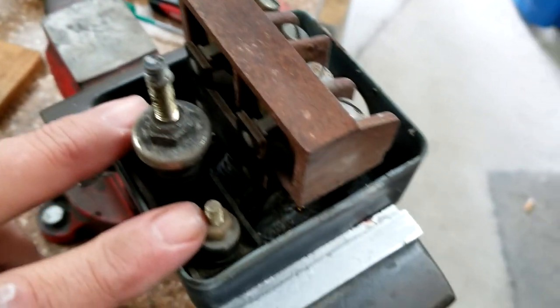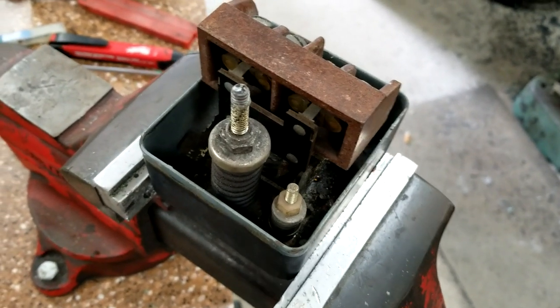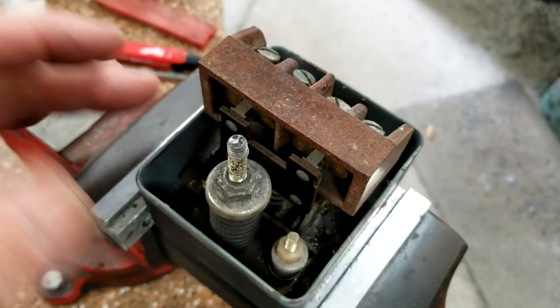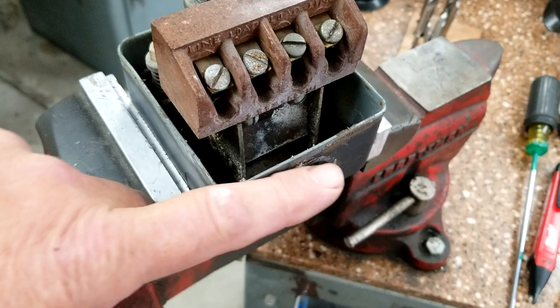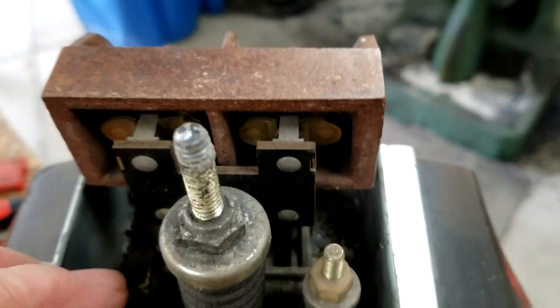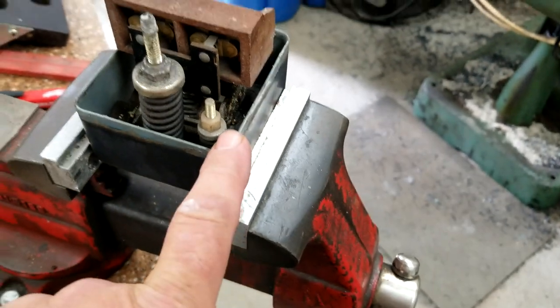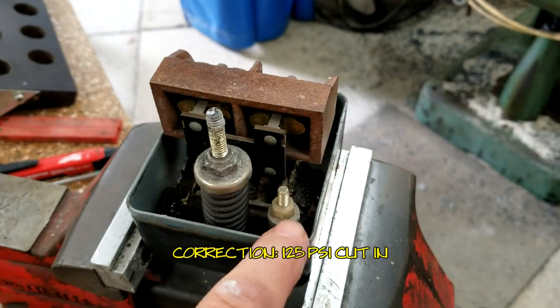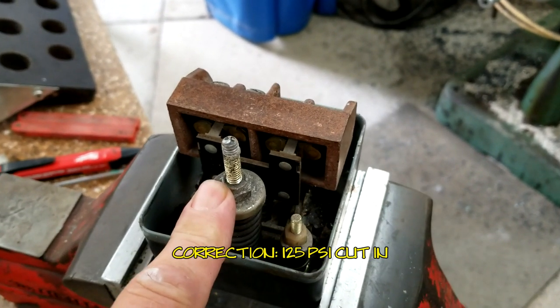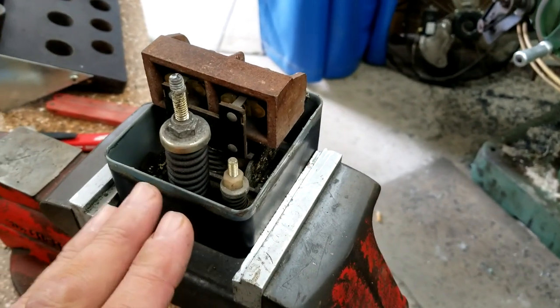We got the pressure switch off and it's on the bench. It's old. There are many different types — this is a differential type with two adjustments: one is your cutout and one is your dead band. Some have a pressure relief valve, some have a control lever for big-box-store compressors. This is a two-pole type, meaning there are two sets of contacts, and I can manually operate them. I have mine set for 175 cutout and 125 cut-in.